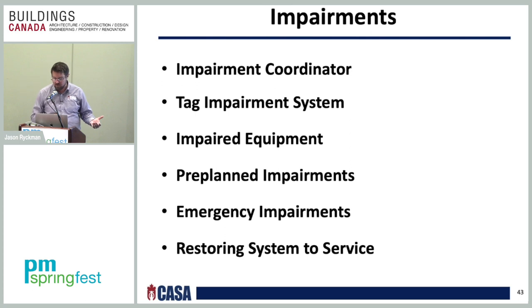The success of any impairment program is determined by the support it receives from those responsible for implementing it. Okay? Often the best way to ensure that an impairment program is properly set up is to review it with the authority having jurisdiction, which can be the fire department, the insurance company, or other officials. If any situations arise that are not covered by the impairment program, it is good practice to seek advice from the authority having jurisdiction.